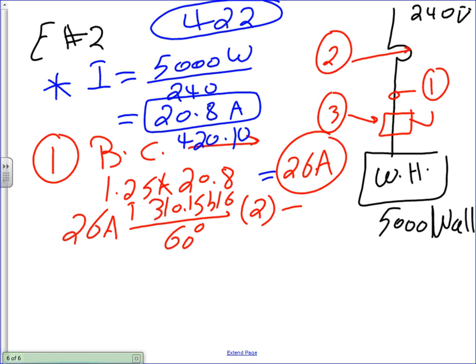Two conductors, number 10 AWG. Now this could be an NM cable because it's the 60-degree column, or it could be a THHN, because THHN can also be sized under a 60-degree column, right? And most likely if it's residential, it's going to be an NM cable, 60-degree column. Okay, now we size it. We'll come to the ground in a second.